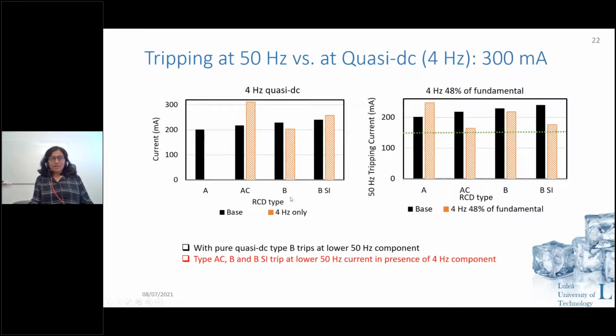Then next is 50 hertz tripping for 300 milliampere. For 300 milliamperes, we have different types of RCDs: A, AC, B, and BSI. Type A RCDs do not trip for the 4 hertz component, and they are not even meant to trip. And that is one of the major problems. If you have type A RCDs, they do not detect DC or even quasi-DC components. So they did not trip.